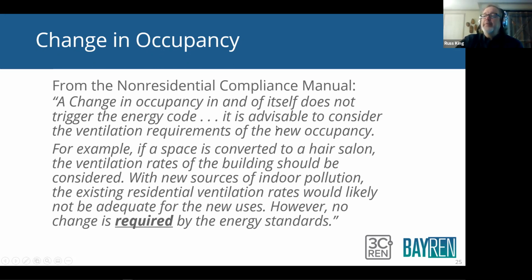It is advisable to consider the ventilation requirements of the new occupancy. For example, if a space is converted to a hair salon, the ventilation rates of the building should be considered. With new sources of indoor pollution, the existing residential ventilation rates would likely not be adequate for the new uses. However, no change is required by the energy standards, all right? So you kind of have to look at the mechanical code in that situation, right?